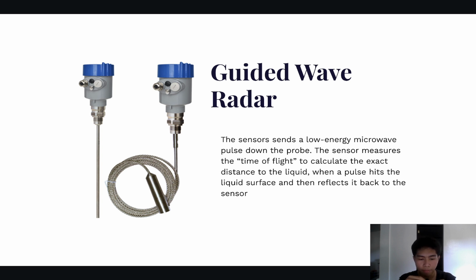Though the probe is in physical contact with the liquid, what measures the level of the liquid beverage inside the storage as well as the container where the liquid beverage will be put is the sensor. It emits a microwave down the probe, and once it hits the liquid beverage, it reflects back to the sensor, which calculates the time of flight, determining what level the liquid beverage is at the moment.